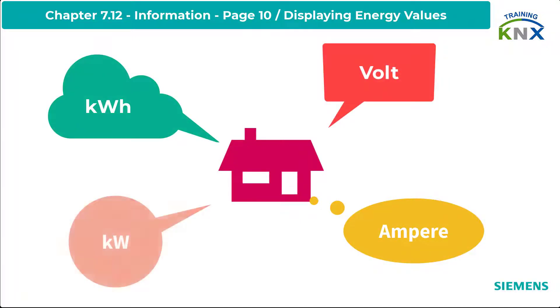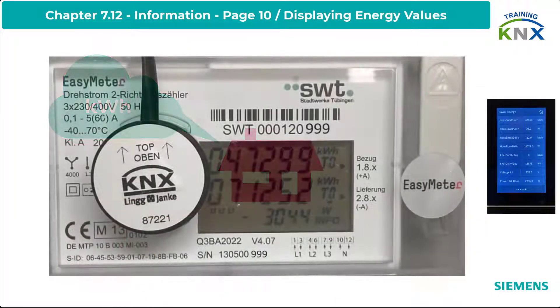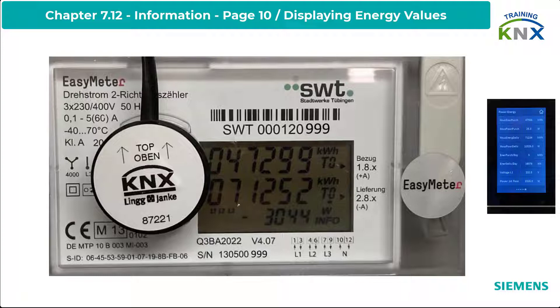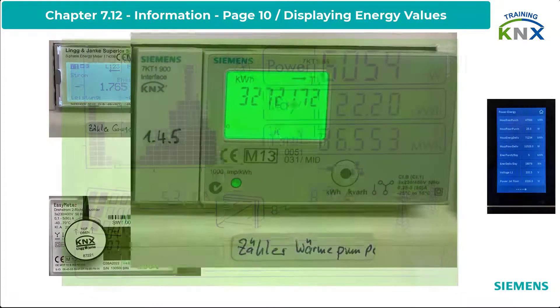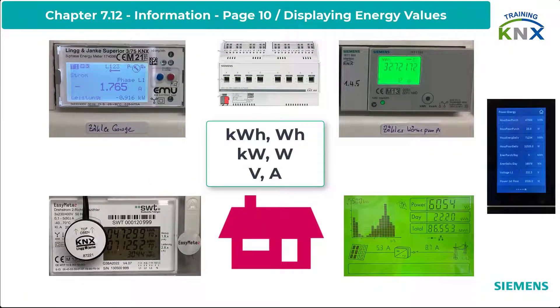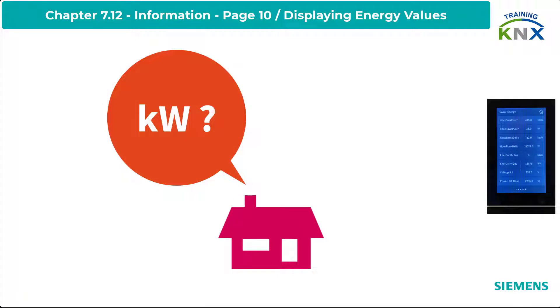Anyone who operates a smart building also wants to check the current status of the consumption meters from time to time. After all, you no longer have just one official calibrated electricity meter from the power supplier, but sub-meters that count the active energy per phase, or even individual consumers. They are energy actuators that provide an energy meter and instantaneous power measurement per channel, because beside the consumption, the current power is also of interest.